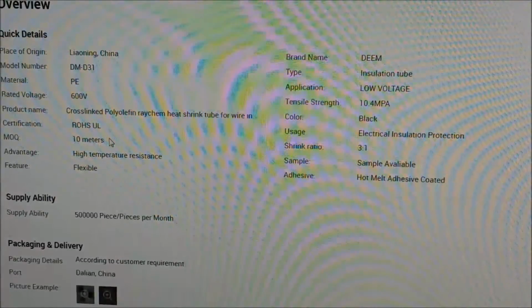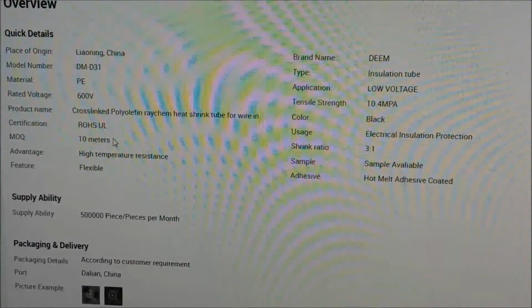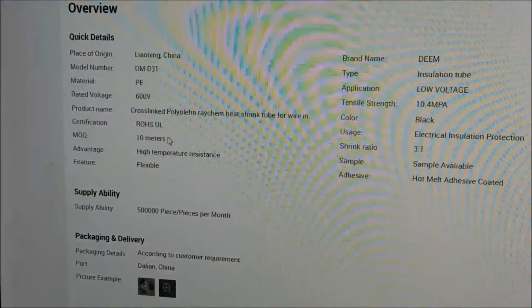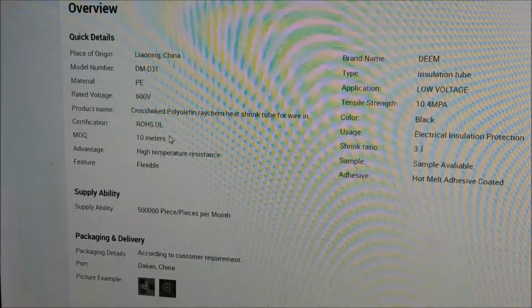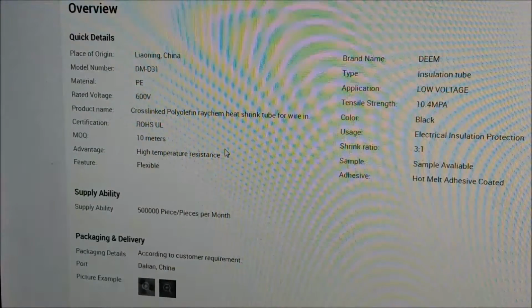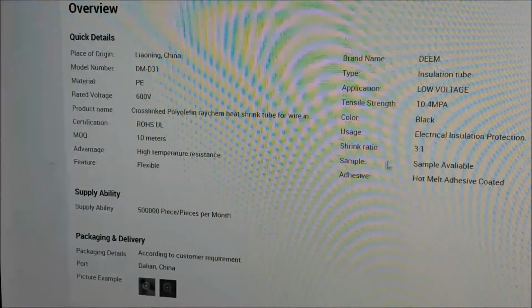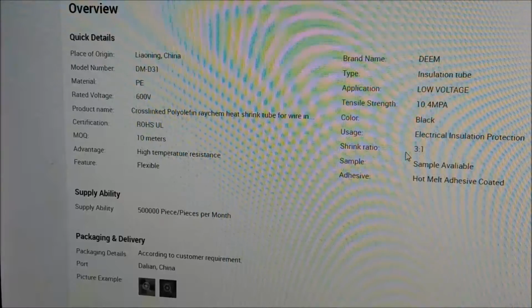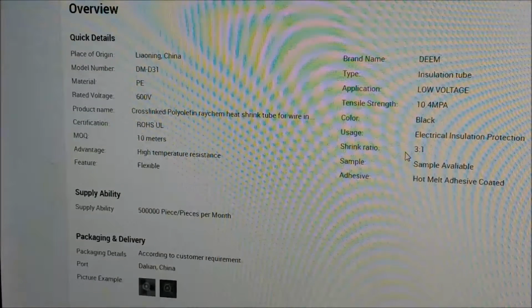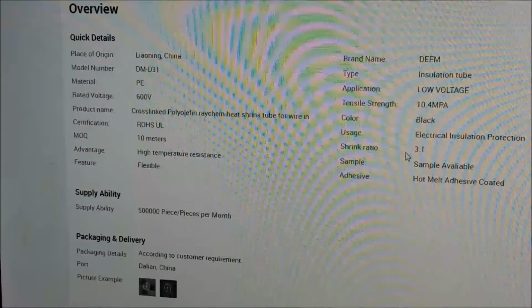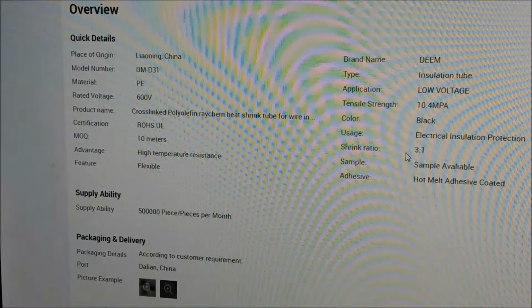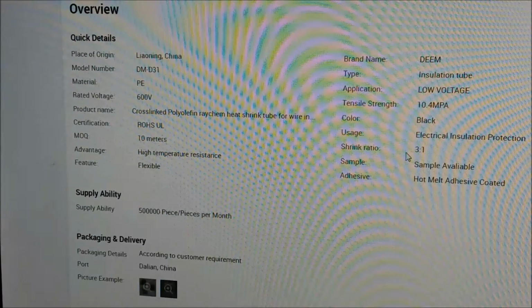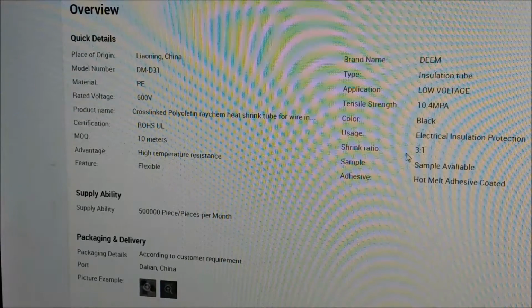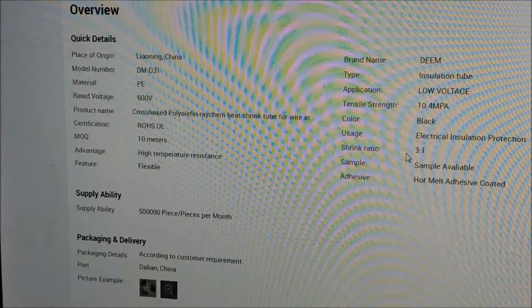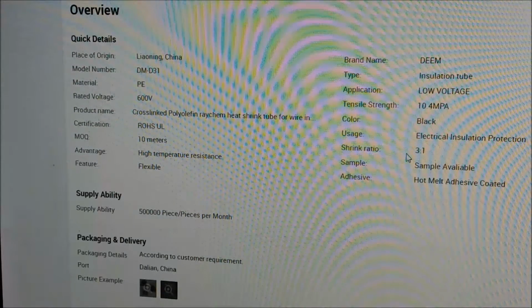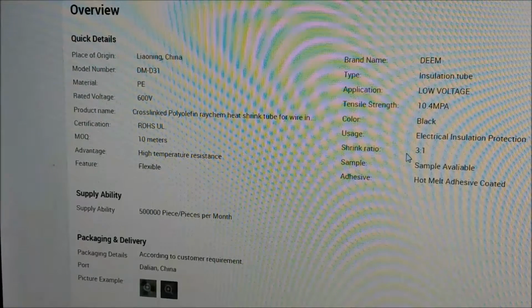This is a product spec: cross-linked polyolefin heat shrink tube, certified ROHS and Underwriters Laboratory. This one's 600 volt in black. Shrink ratio — when you get one that shrinks 3 to 1, like if it's 3/4, it'll shrink down to 1/4. What that does for you is the wall thickness goes up by 3, because there's the same amount of material there. It shrinks mostly in the width, only about 3% in length, but shrinks all of the width. So when you get a double wall with adhesive, 3 to 1 is about the go-to size. You can get 4 to 1 without adhesive — it'll shrink to 1/4 its size.